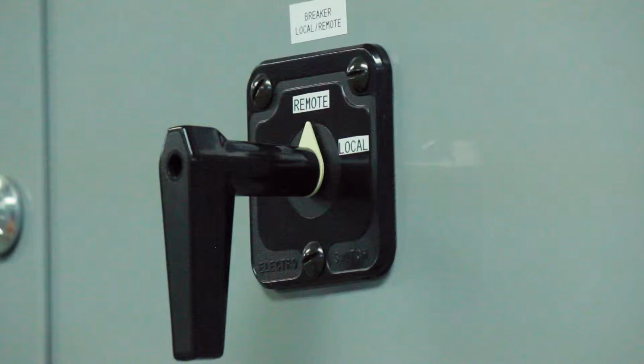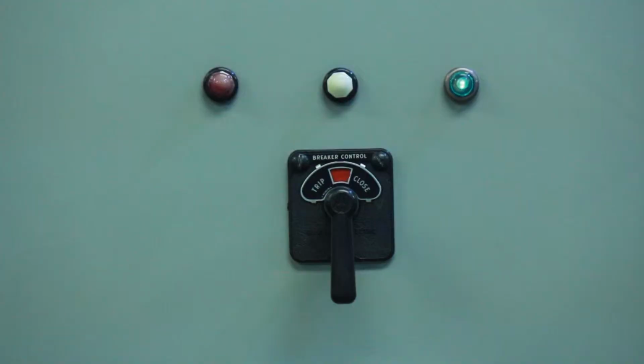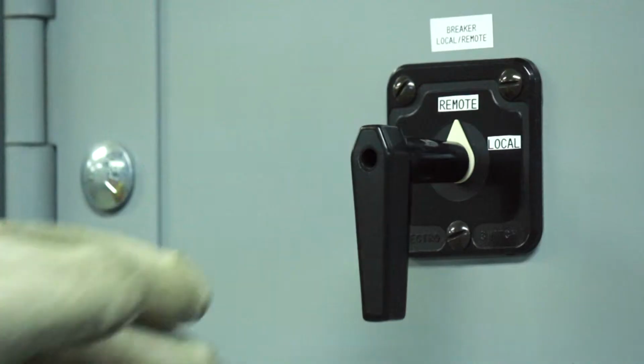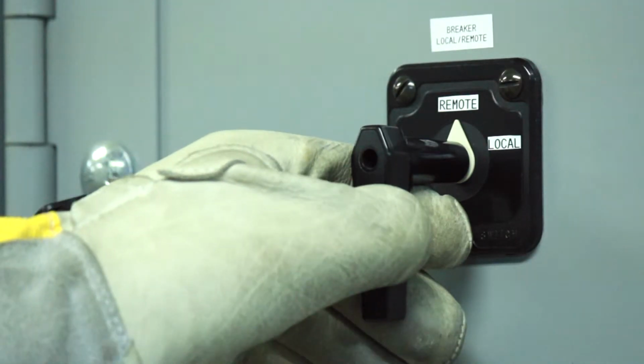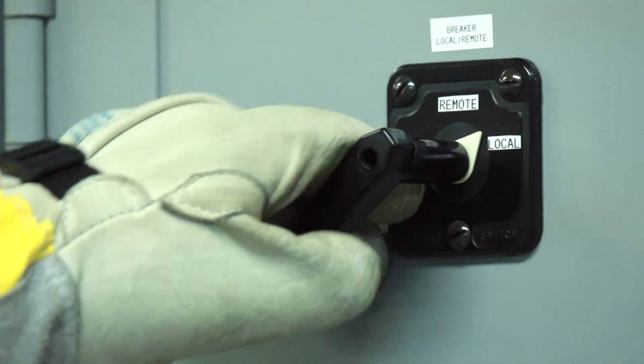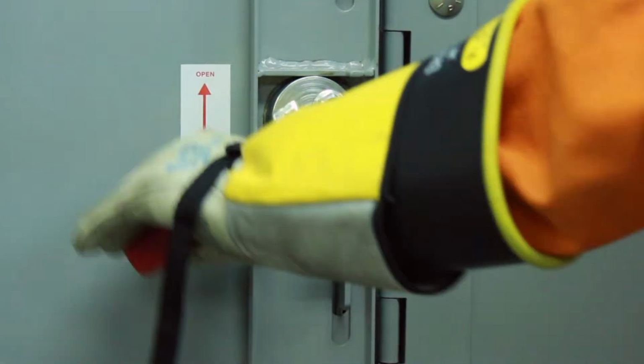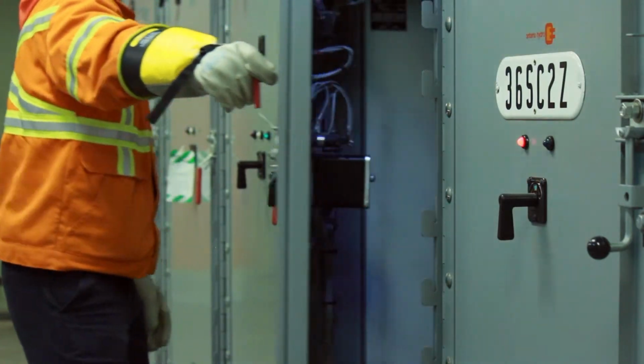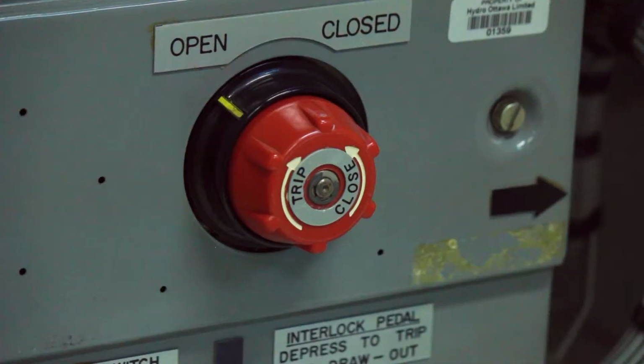Verify the breaker panel is in the remote position and call System Office to have them remotely open the circuit breaker. The breaker indicator light will switch from green to red, indicating the breaker is now open. Before you disconnect the breaker, switch the operating control from remote to local. Verify that the breaker is now open by the red indicator control dial.